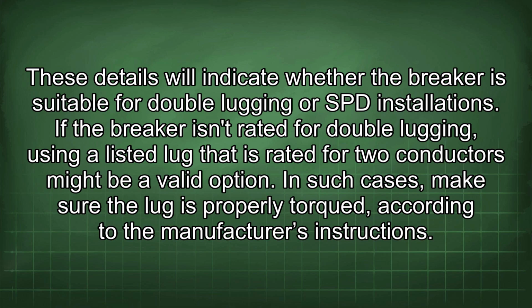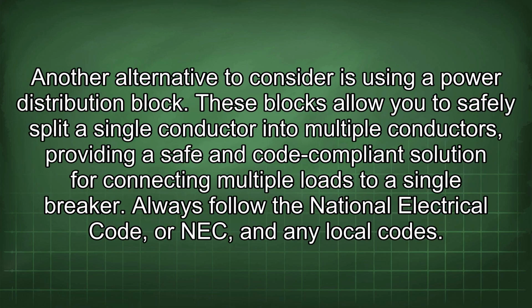If the breaker isn't rated for double lugging, using a listed lug that is rated for two conductors might be a valid option. In such cases, make sure the lug is properly torqued according to the manufacturer's instructions. Another alternative to consider is using a power distribution block. These blocks allow you to safely split a single conductor into multiple conductors, providing a safe and code-compliant solution for connecting multiple loads to a single breaker.